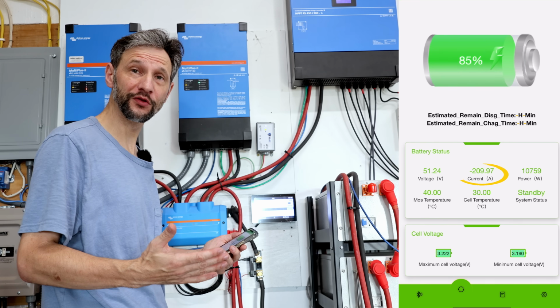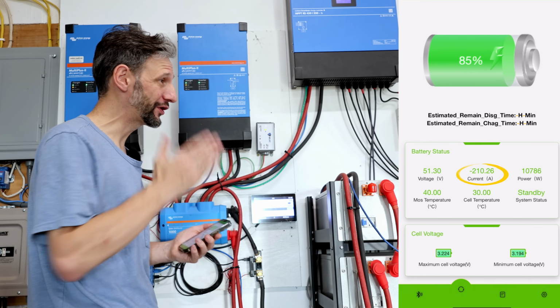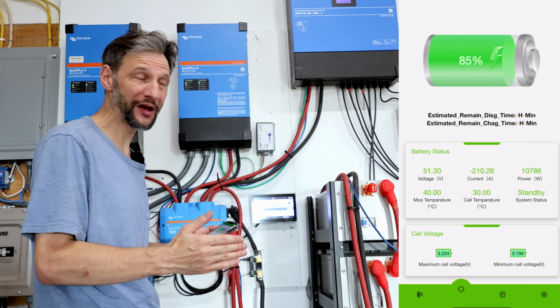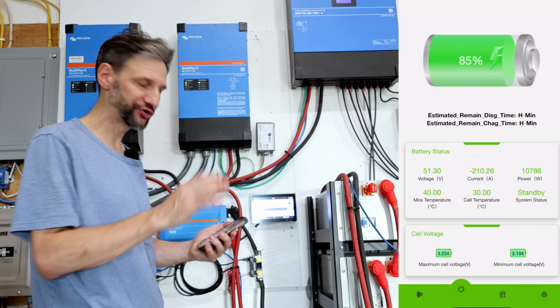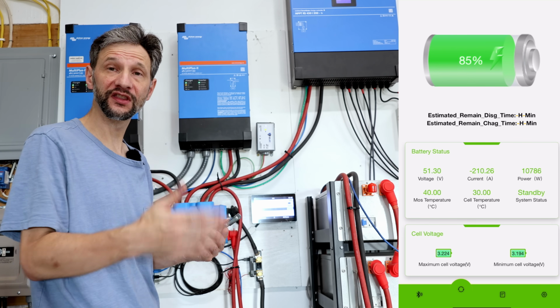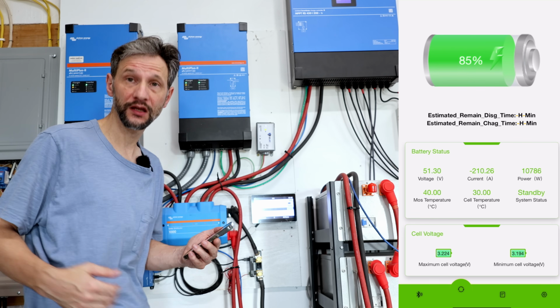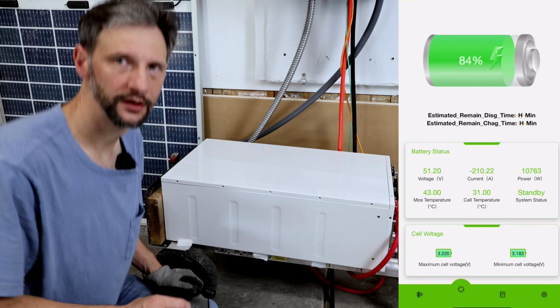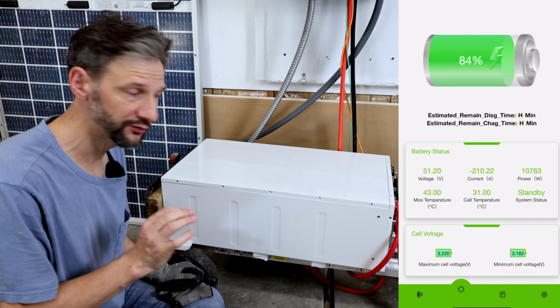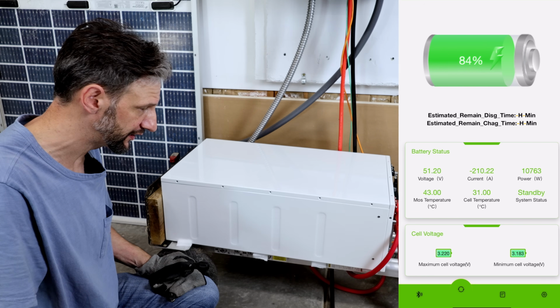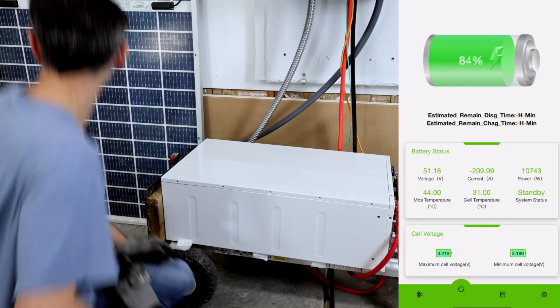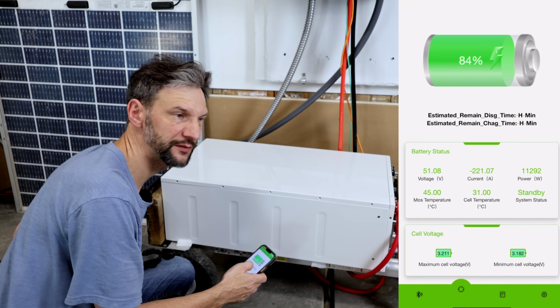Well, it's showing a little over 200 amps as well. That's great. So this is slightly over the maximum output. I don't know how long it'll let it run. I'm sure there'll be some limits on that. So let's get the infrared camera out and see what it's looking like while it's at its limit. I'm going to back it down just a tiny bit so we don't trip the BMS before we can measure all the heat levels. I hear the BMS beeping.